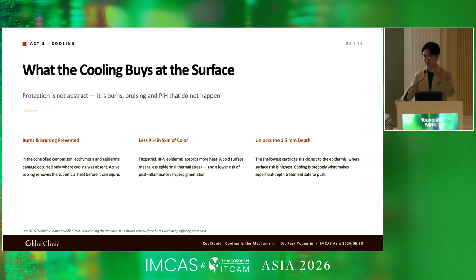So sometimes when we use monopolar RF or maybe very high energy for the HIFU, you might have to decrease the power in those areas. But actually with the cooling of the epidermis, you don't have to worry about too much heat, because the heat generated in the epidermis will decrease, and the PIH that will happen will decrease. And especially for the epidermis saving, especially for 1.5 energy. Because as you know, for example, even for maybe Thermage, you only use 0.2 joules for the energy for 1.5. It's because there might be a high chance of getting burning or complication, because the heat will be going to the surface as well while the shot accumulates.